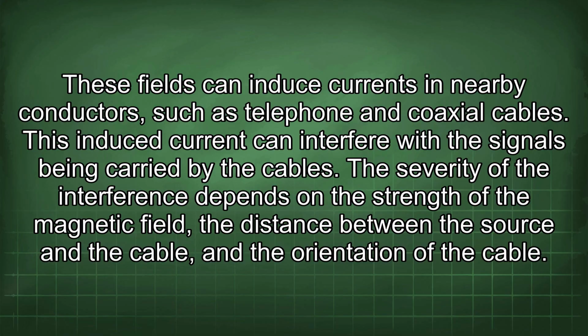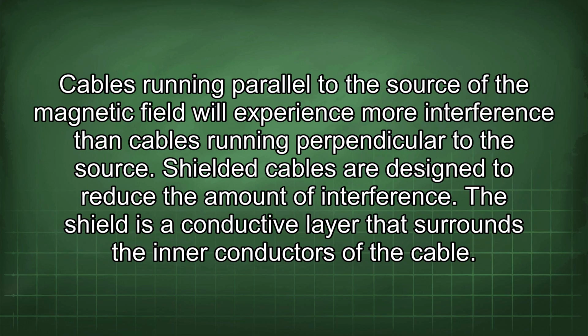The severity of the interference depends on the strength of the magnetic field, the distance between the source and the cable, and the orientation of the cable. Cables running parallel to the source of the magnetic field will experience more interference than cables running perpendicular to the source. Shielded cables are designed to reduce the amount of interference.